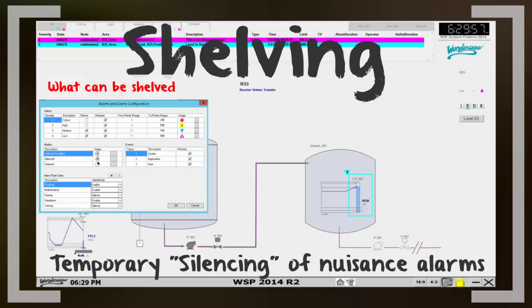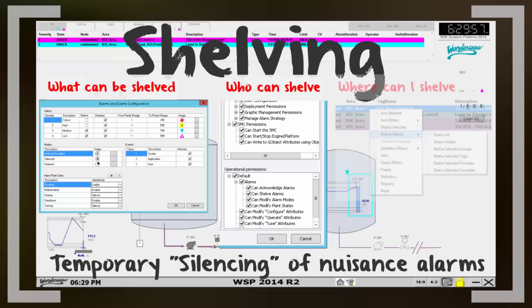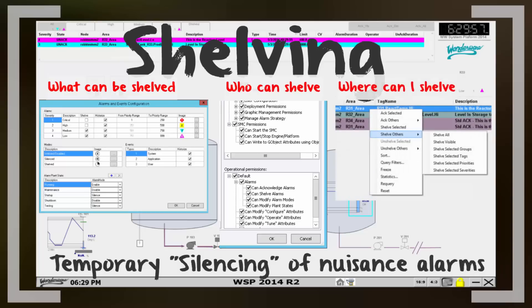The software has been enhanced to add configuration parameters that enable or disable the alarm severities that can be shelved. For example, you may not want to allow operators to shelve a high tank level alarm or a fire alarm. You can also control who can shelve alarms — you may only add those capabilities to certain operators. The alarm clients now have the shelving capability built-in, so you don't have to create custom implementations to add this functionality.